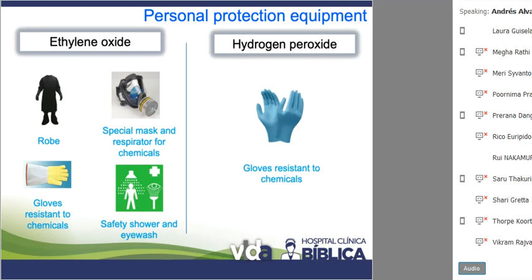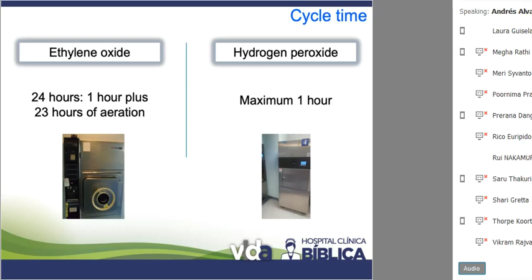Mr. Orris spoke as well related to the ethylene oxide about the cycle time. In this case, for our old equipment, in the case of ethylene oxide, the cycle time was 24 hours, 1 hour, plus 23 hours of aeration. In the case of the hydrogen peroxide, this cycle takes only 1 hour. This is very, very important, related as well, talking about the productivity of the process.